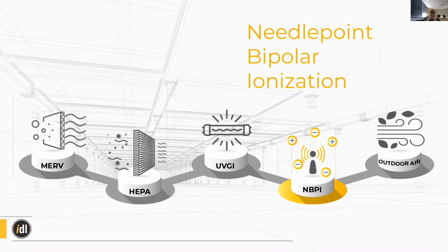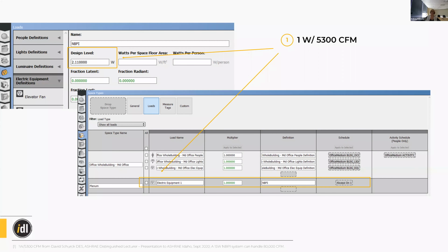Again, it's an emerging technology and the technology is very sound. The issue that we ran into is that there's just not a lot of research right now on how applicable it is, or the efficacy of it, with large volumes of air and fast moving air. So in a commercial HVAC, we know that in theory the technology works. Does it work with HVAC? That is to be determined. But it's worth studying, I think, because the energy impacts are so low. It's really just 1 watt per 5,300 CFM. So much lower than the UV.